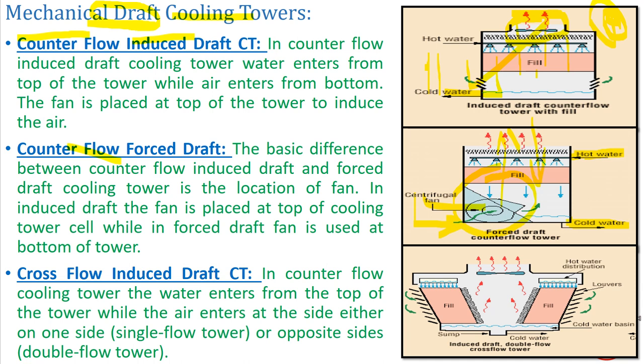Cross flow induced draft cooling towers are among the most widely used types in industry. In cross flow, unlike counter flow, water enters from the top but air enters from the sides of the tower. So instead of a counter arrangement, air crosses the water stream. A fan at the top creates negative suction that draws the air upward and rejects it to the atmosphere.